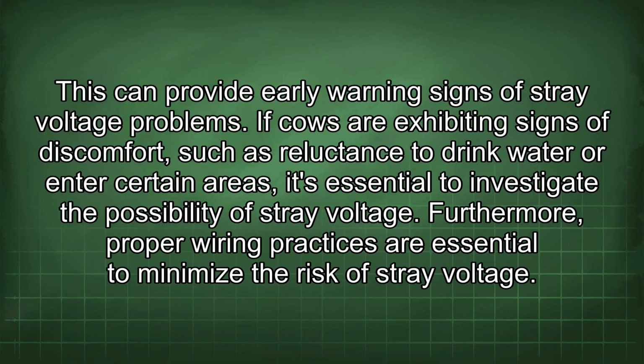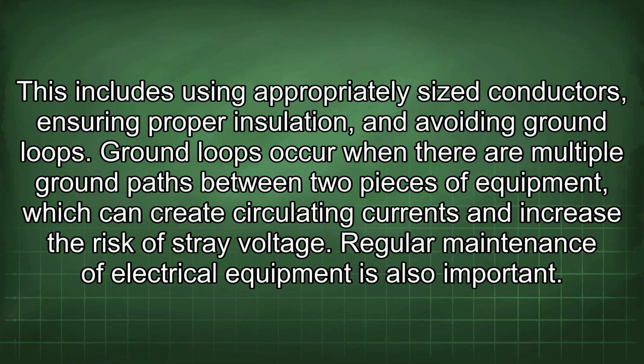Furthermore, proper wiring practices are essential to minimize the risk of stray voltage. This includes using appropriately sized conductors, ensuring proper insulation, and avoiding ground loops. Ground loops occur when there are multiple ground paths between two pieces of equipment, which can create circulating currents and increase the risk of stray voltage.